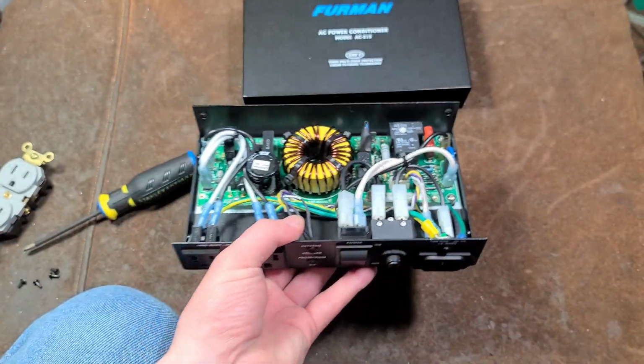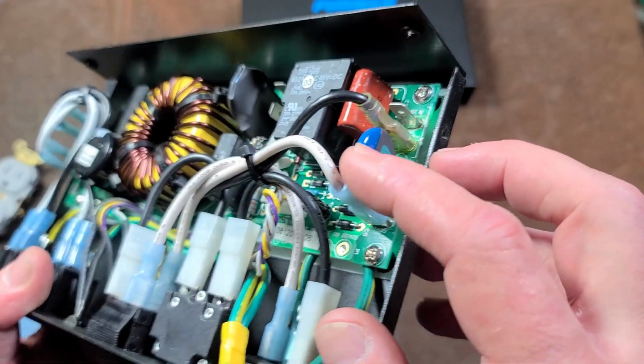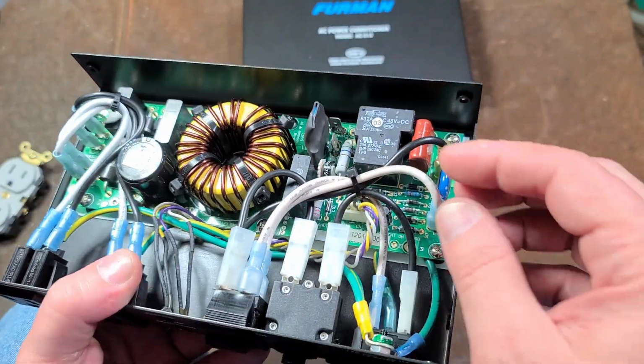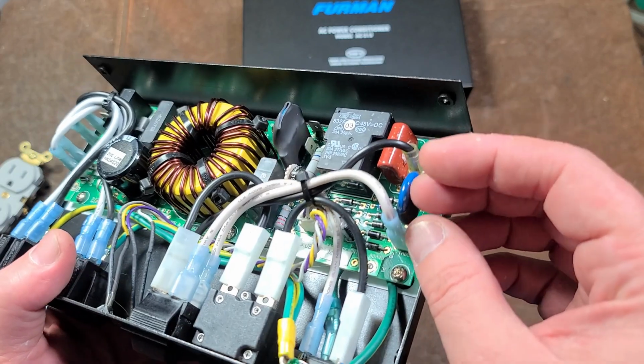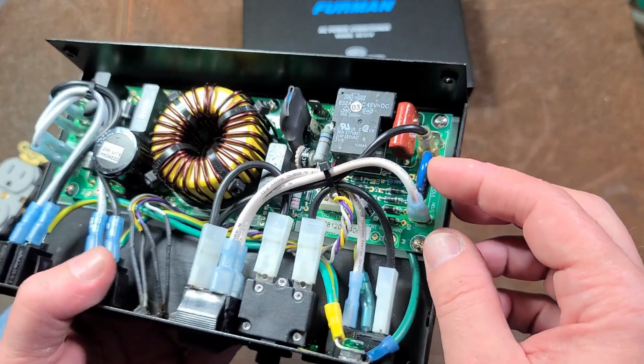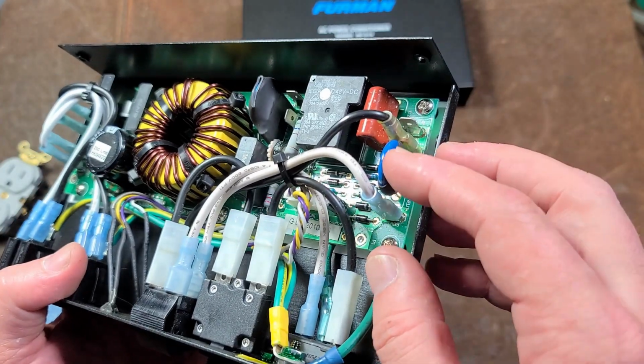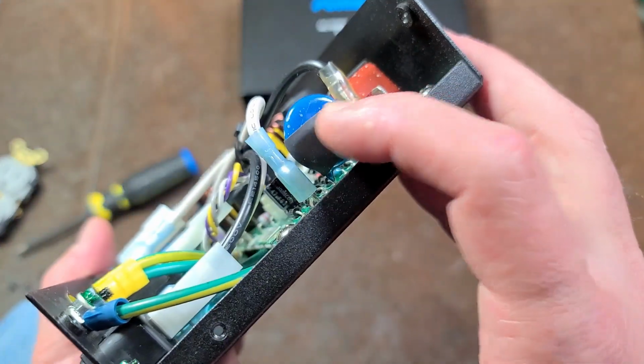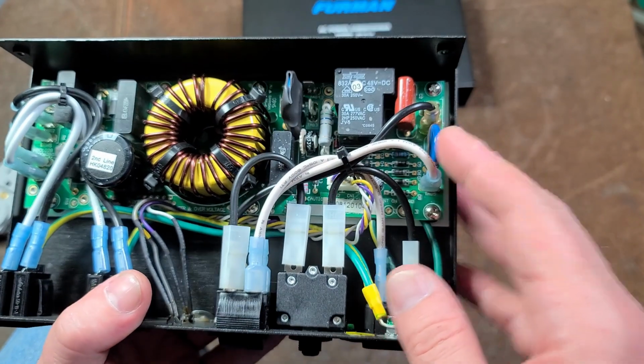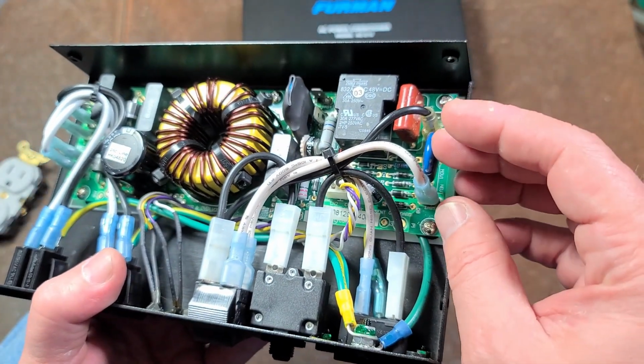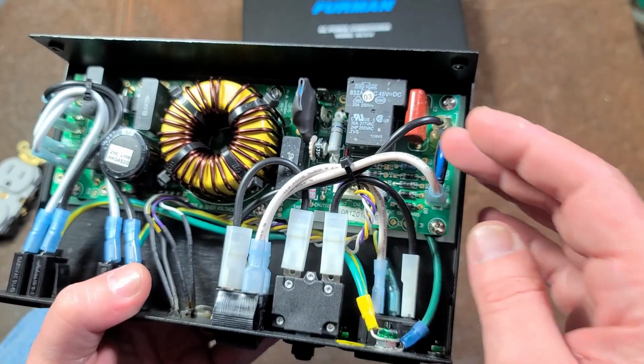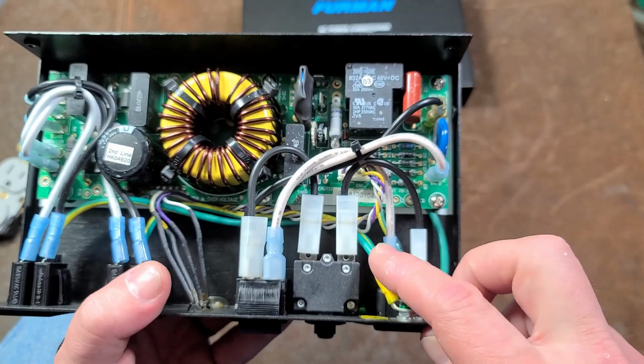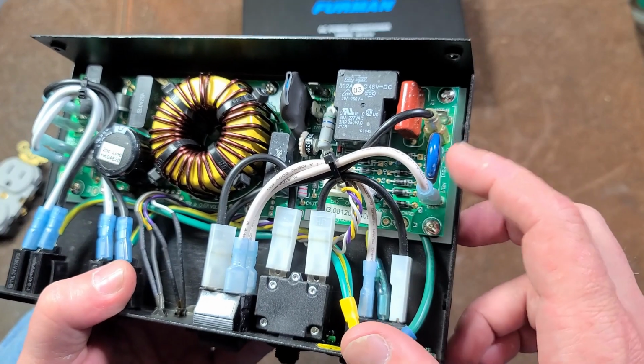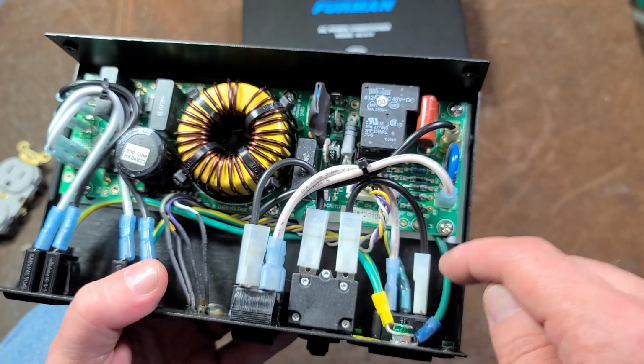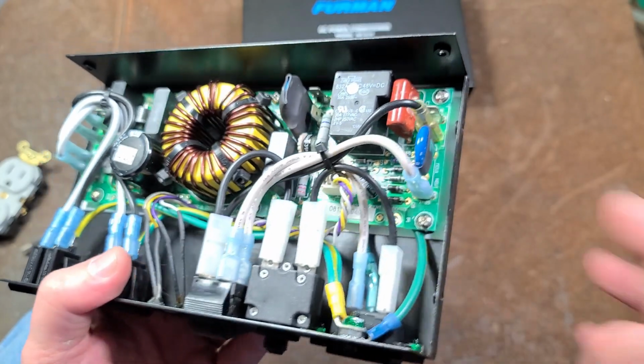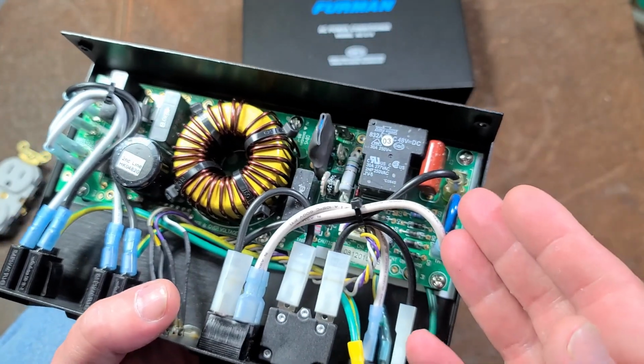They're a special type of resistor, made out of a very special kind of powder, so when you get a big voltage spike, it causes these circuits to essentially short out. Many times they will explode, that's why they put this shrink tubing over them. As they short out, they become conductive and will shunt or drive that pulse back out through the ground wire. So these are connected in from the hot and neutral, and the other end is connected to ground. The problem is, of course, the electronics are ruined.